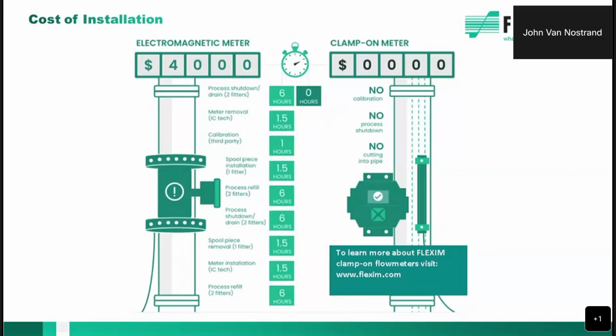Another thing to consider when you're looking at a FLEXIM meter versus a Magmeter, it'll average about $4,000 to install. I've seen it as high as $13,000. And then you look at the number of downtime hours that you're going to have. Typically about all day is what it takes to install, unless you're in a situation where they're very large pipes, then it can take several weeks. Not to mention the lead time to get a Magmeter.